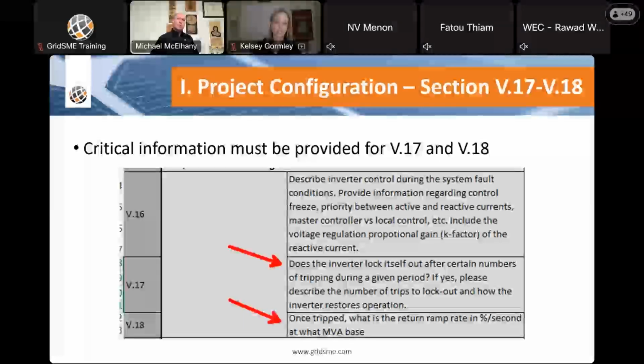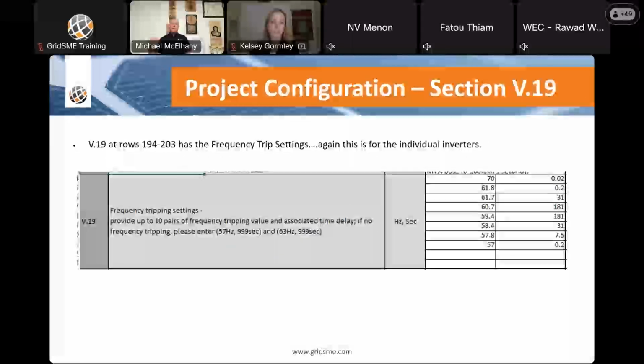And then once tripped, what is the ramp rate in percentage per second? The CAISO Appendix H requirement is 100% per second. We've had some where we catch it saying 100% per minute, or some other number that isn't 100% per second. That is a hard and fast requirement, and that's where that comes into play. And then there are inverter settings and other documentation that can show that as well. The next slide is just another one that we double check because it's exposed.